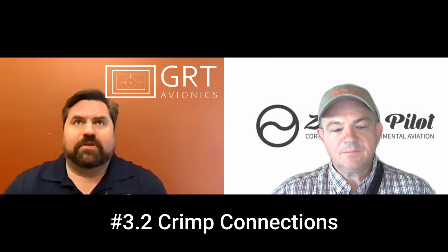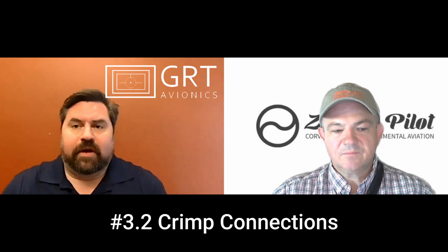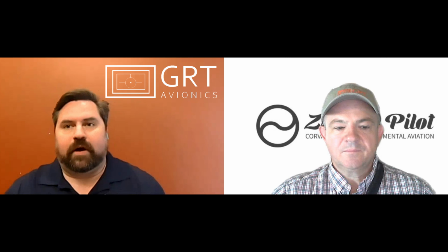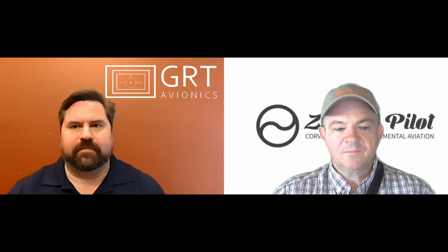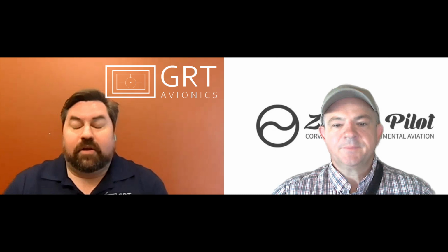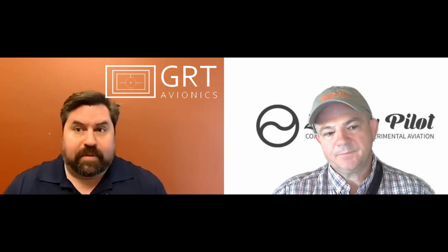A pin can be crimped onto a wire, and it can look like it has a good crimp, but all those wires are stranded wires, so it's not just one solid piece of copper. It's many little pieces of copper, which makes the wire more flexible and less likely to break. But it can also make it harder to get a good crimp.